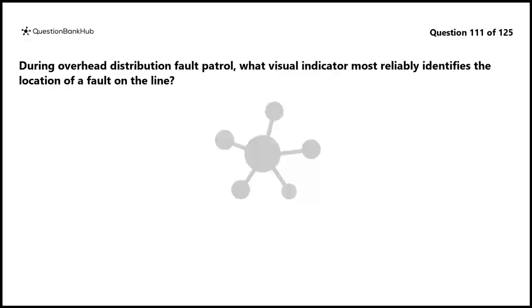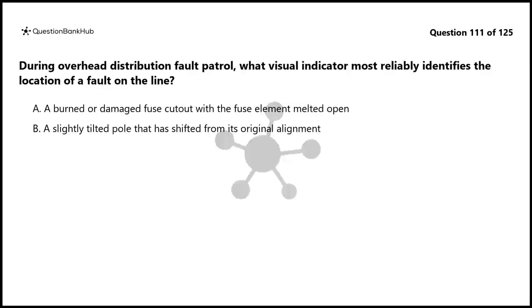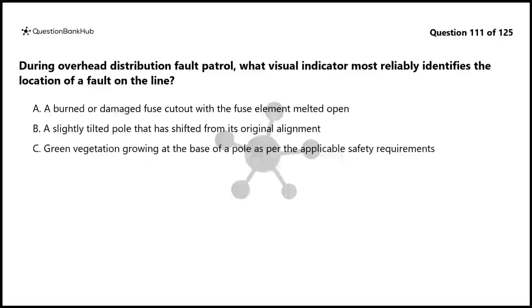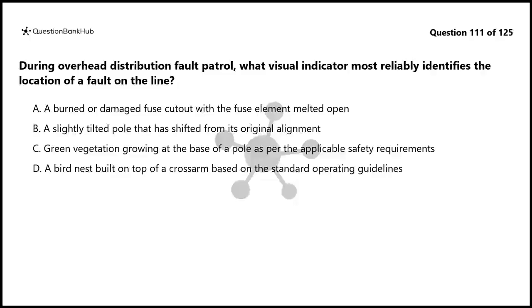Question 111. During overhead distribution fault patrol, what visual indicator most reliably identifies the location of a fault on the line? A. A burned or damaged fuse cutout with the fuse element melted open. B. A slightly tilted pole that has shifted from its original alignment. C. Green vegetation growing at the base of a pole as per the applicable safety requirements. D. A bird nest built on top of a crossarm based on the standard operating guidelines.